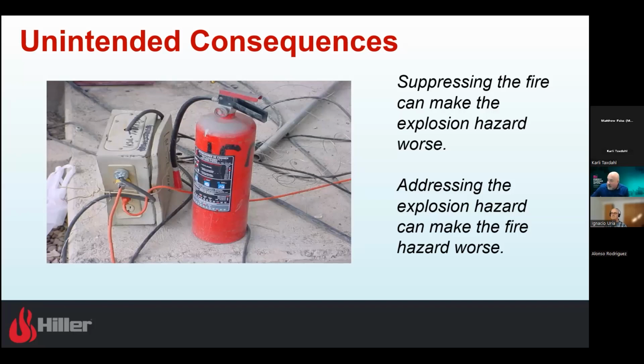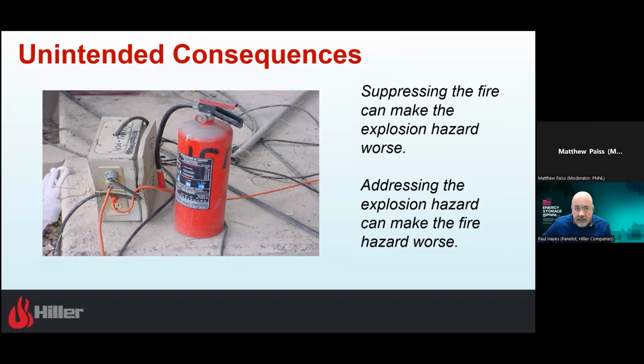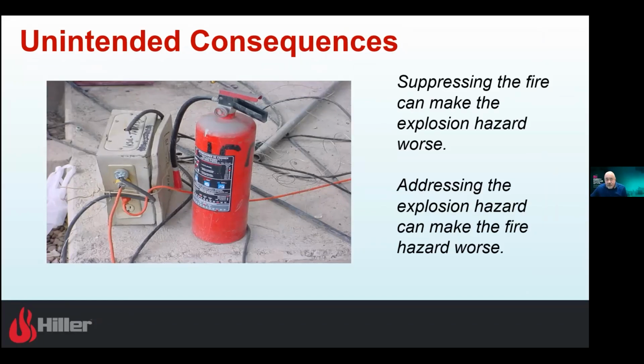This is one of my favorite pictures in the world, and I always show it because of unintended consequences. This was a power site that needed power, so they brought it out there, and apparently it caught fire, so somebody added a suppression system. Now, the unusual thing we run into with batteries is that by suppressing the fire, we can make the explosion hazard worse. By addressing the explosion, we can make the fire hazard worse. So it's not always an easy solution of what is the higher risk.